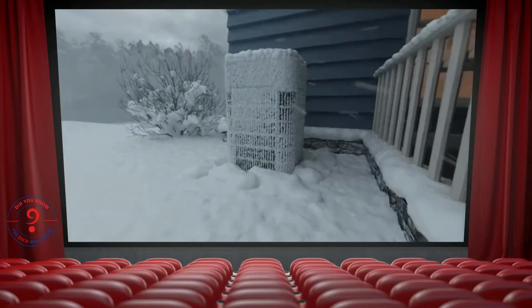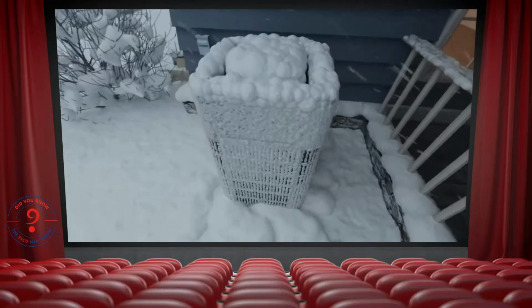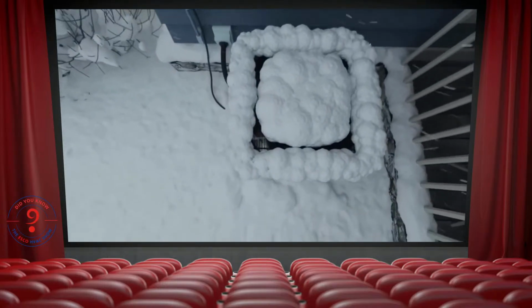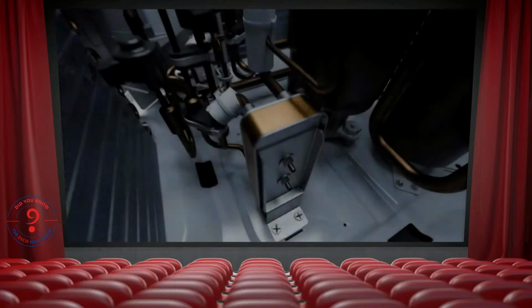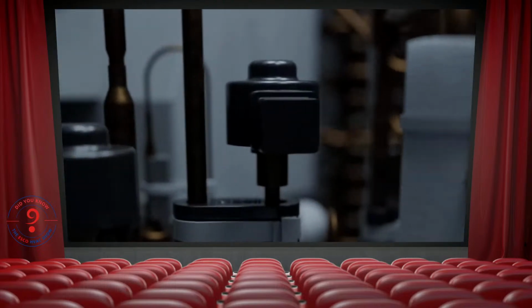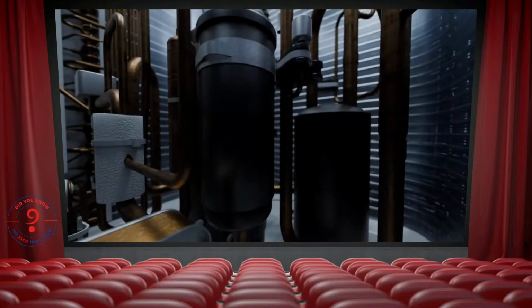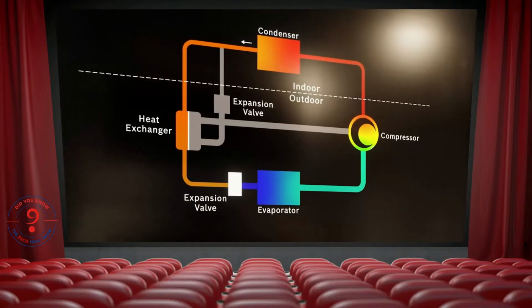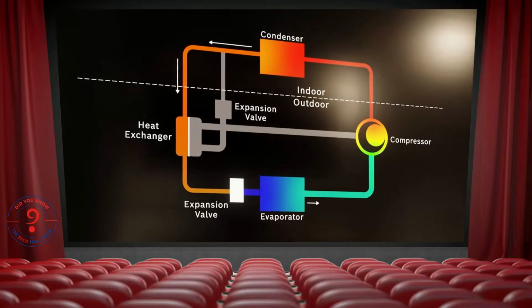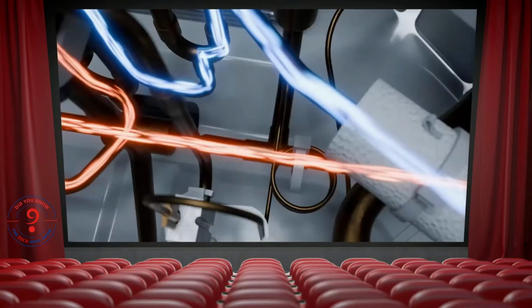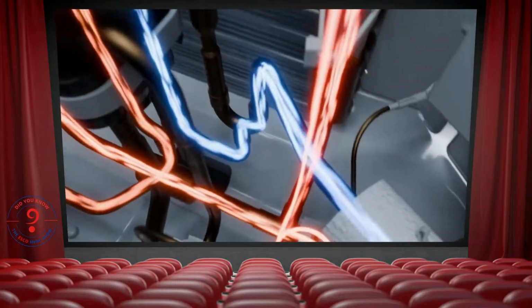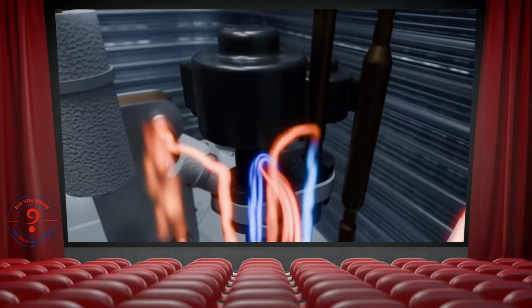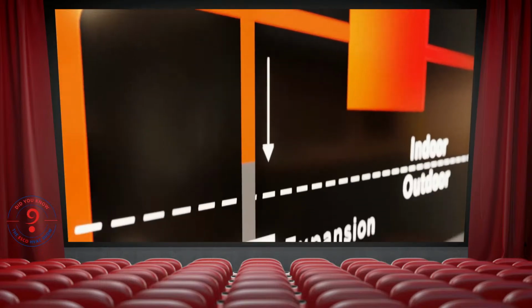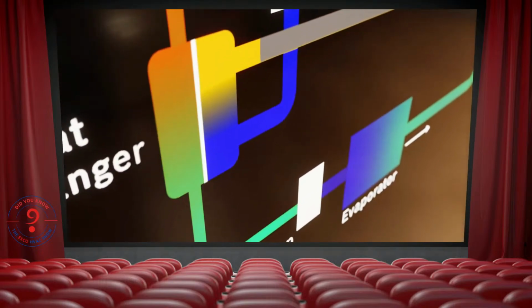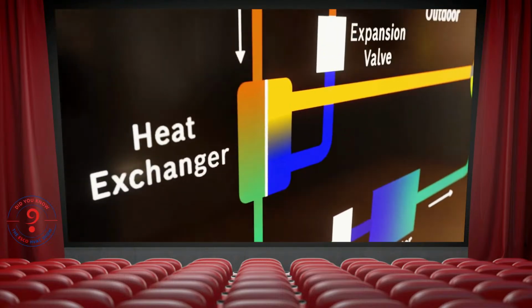The new Bosch IDS Ultra features an innovative technology called enhanced vapor injection to enable efficient heat pump operation in cold climates. Enhanced vapor injection is enabled by the addition of a plate heat exchanger, an additional electronic expansion valve, and complemented by an inverter compressor. The system operates much like a conventional heat pump. When additional capacity is needed at very low temperatures, an expansion valve opens to allow a portion of refrigerant to bypass the traditional cycle. The vapor injection process begins as a portion of the liquid refrigerant is diverted through an expansion valve into the intermediate heat exchanger, transforming it into a cool vapor.